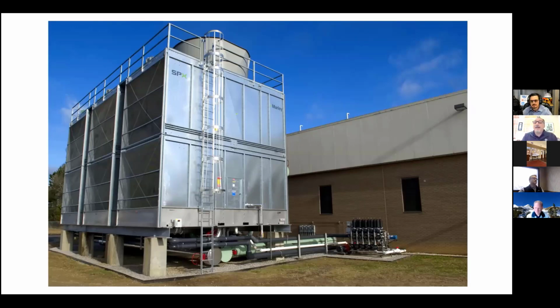So if you really want to enhance a cooling tower sump to really clean it out, instead of running that 286, it could be for each tower here, maybe you shut one off and really blow off the other tower. It really gets it nice and clean. And you could do that periodically to really clean the basin itself. But in this case, it's a turbo disc taking off the equalizer piping, not the sump itself or the reservoir underneath the tower. That's a very nice installation right there.